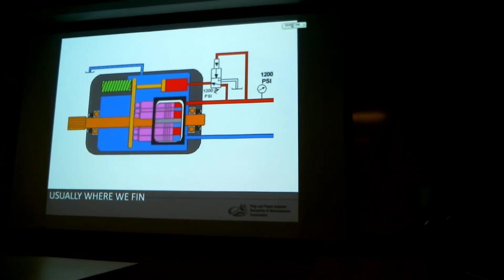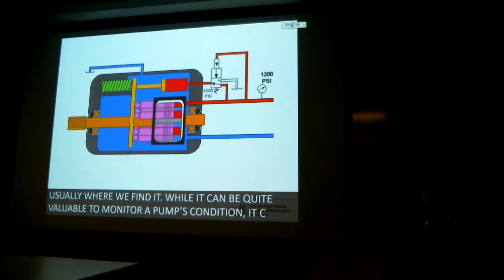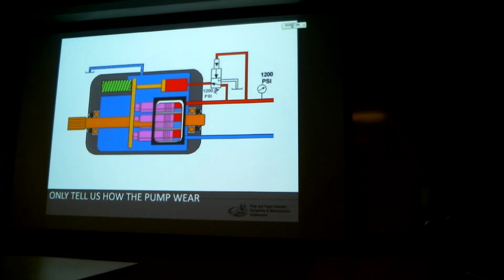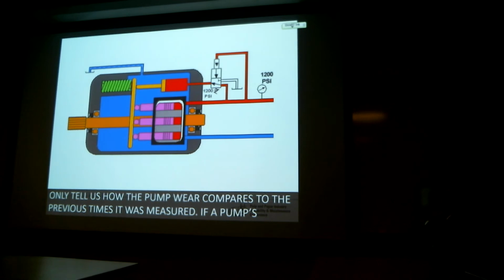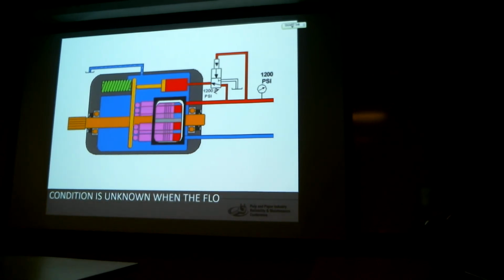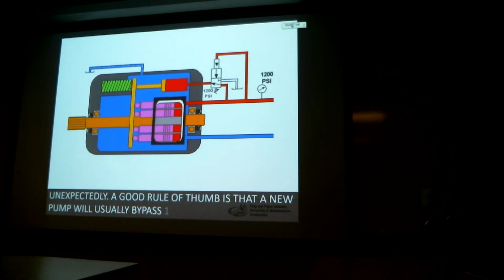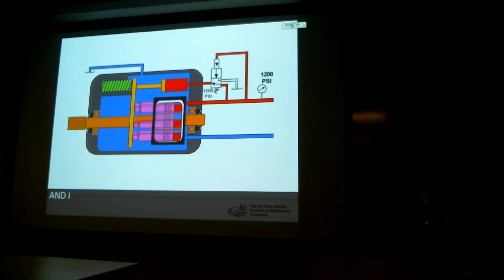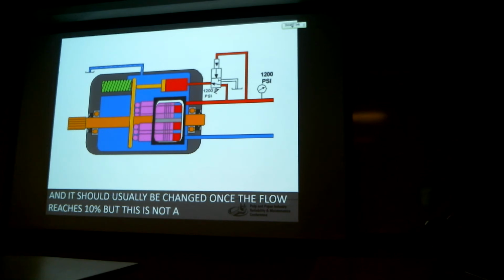While it can be quite valuable to monitor a pump's condition, it can only tell us how the pump wear compares to the previous times it was measured. If the pump's condition is unknown when the flow meter is first installed, the pump could still fail unexpectedly. A good rule of thumb is that a new pump will usually bypass 1 to 3% of its total flow, and it should usually be changed once the flow reaches 10%, but this is not a hard and fast rule.